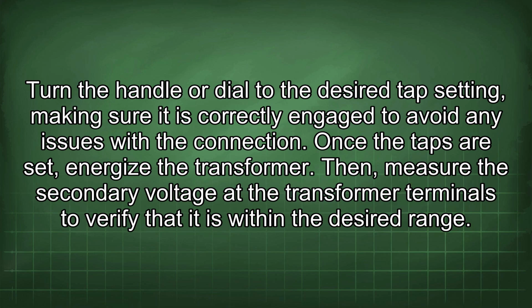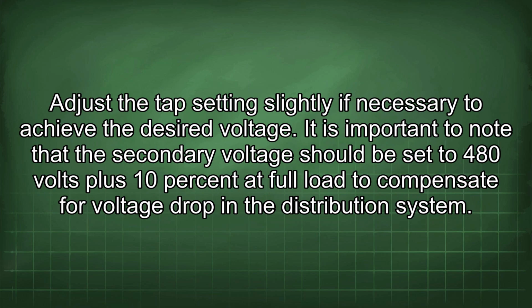Then measure the secondary voltage at the transformer terminals to verify that it is within the desired range. Adjust the tap setting slightly if necessary to achieve the desired voltage. It is important to note that the secondary voltage should be set to 480 volts plus 10% at full load to compensate for voltage drop in the distribution system.